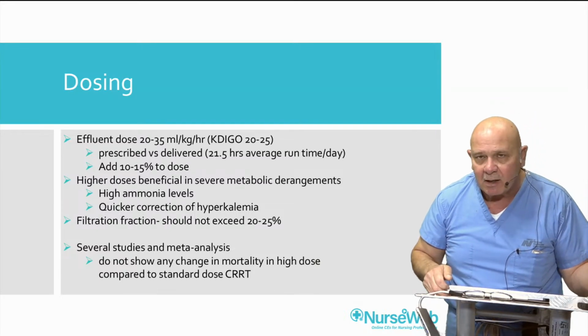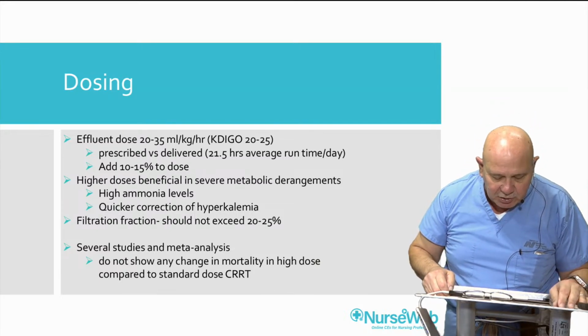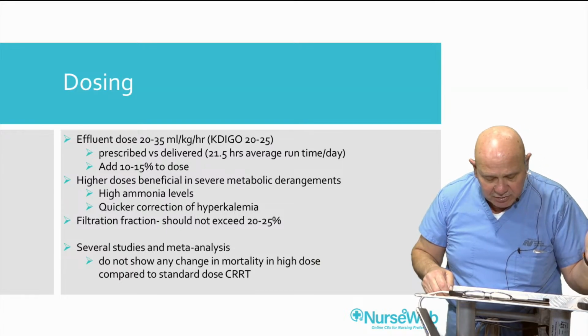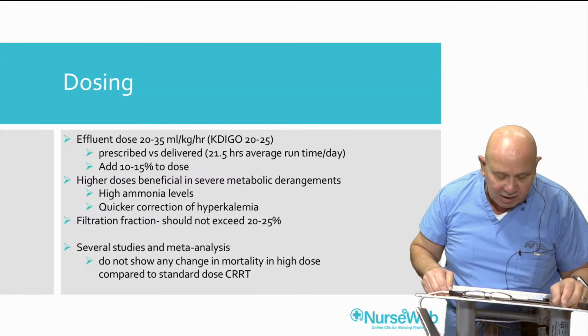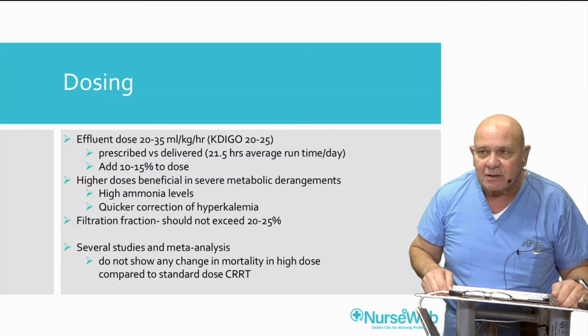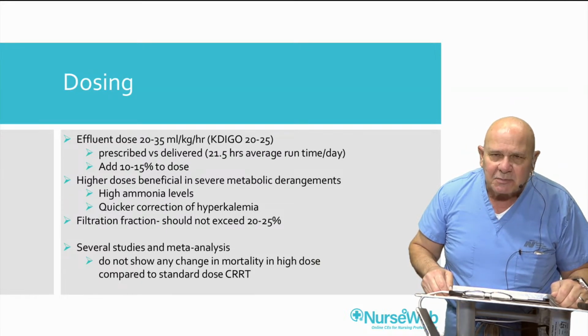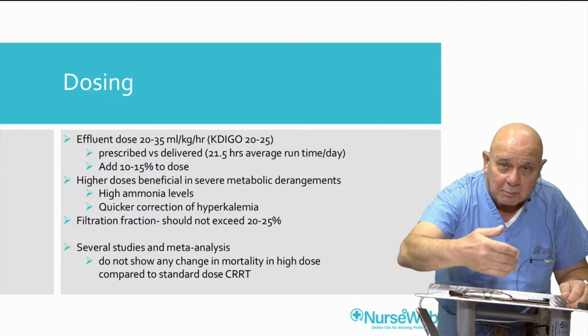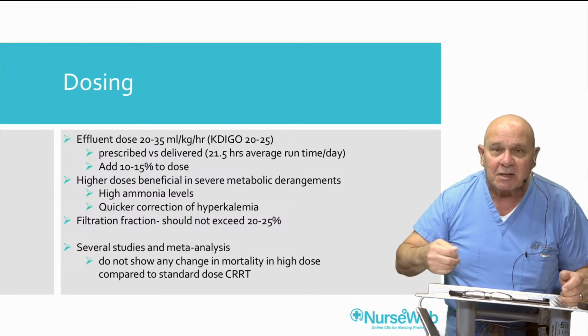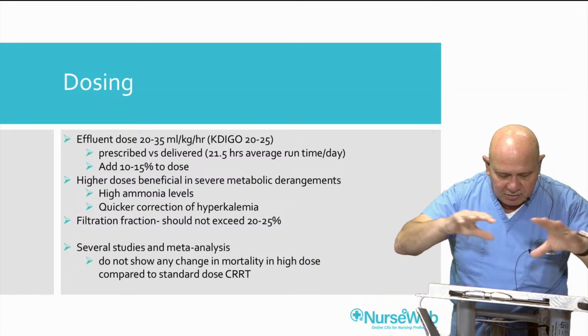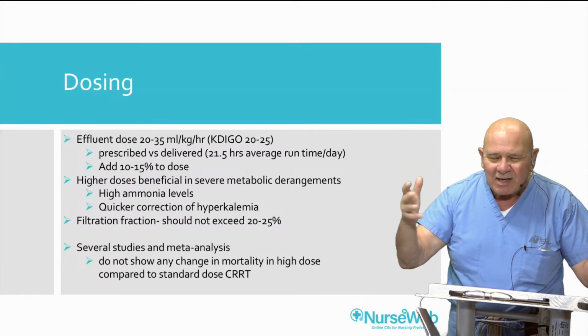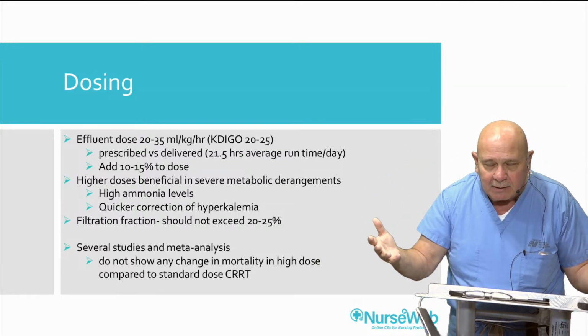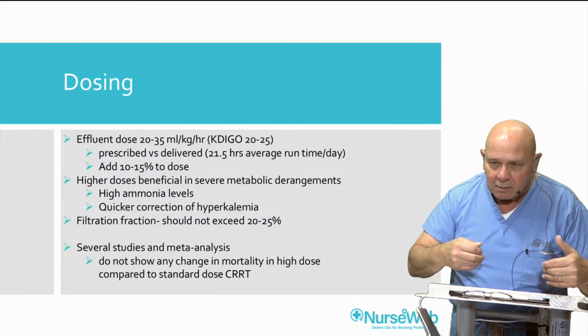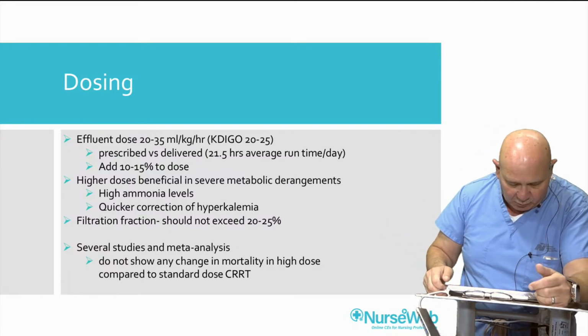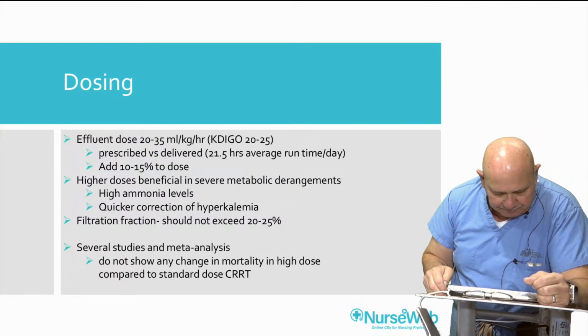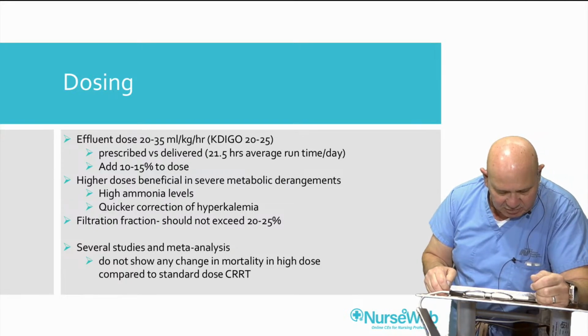So if the patient weighed 100 kilograms and you wanted to do a higher dose, 35 milliliters per kilogram per hour, your replacement has to be 3,500 milliliters per hour, which means your removal, your effluent dose, is going to be 3,500. So there's all these terms, but they all basically mean the same thing. There's just different ways of saying it, if you will. I'm not sure, prescribed versus delivered.